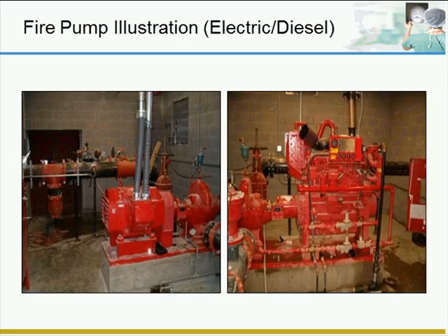If your healthcare facility has a fire pump, it is because the water pressure in your area is not adequate to supply the demand of your sprinkler system. The fire pump actually boosts the pressure of the system. Fire pumps also require inspection, testing, and maintenance. The electric fire pump should be run once a month for approximately 20 minutes with no flow. The diesel fire pump should be run weekly, again with no flow, for approximately 20 to 30 minutes. Your sprinkler contractor or fire pump maintenance contractor can train a member of your staff to conduct this important test.